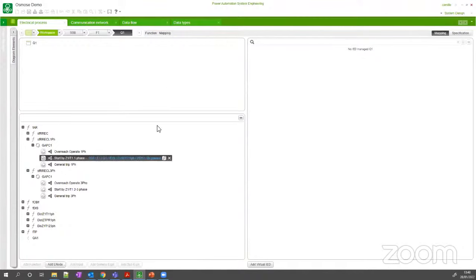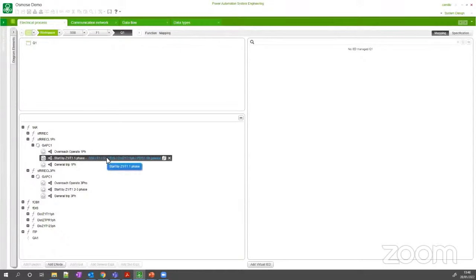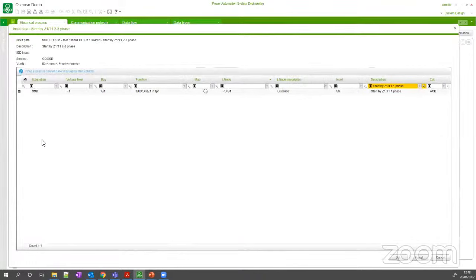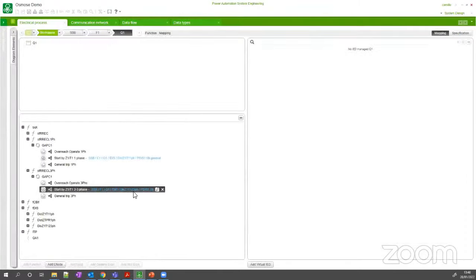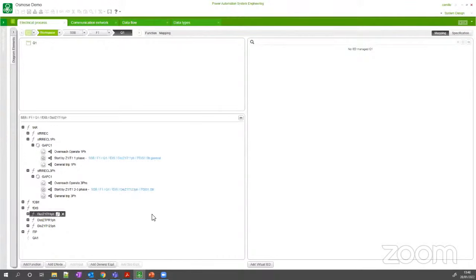In this new interface, I can see all the data available in my configuration. To fill a specific input of my auto-recloser, I search by description — thanks to good naming in the original specification, I can directly find the data to use. So at the specification level — with no IED yet — I know that in bay Q1, function F-AR for auto-recloser, one-phase auto-reclosing, I am receiving data coming from substation B, function F1 in the same bay Q1, from zone one one-phase protection: the trip general. I do the same for the three-phase reclosing, receiving the start from three-phase zone one.